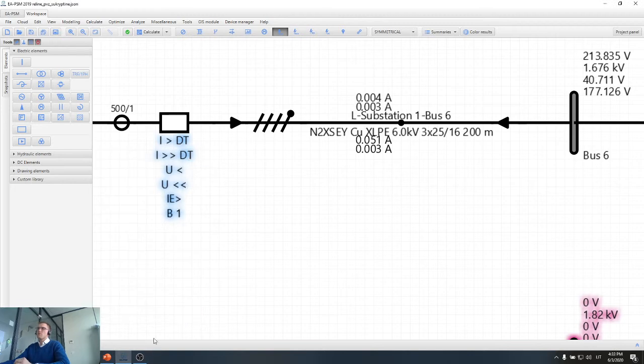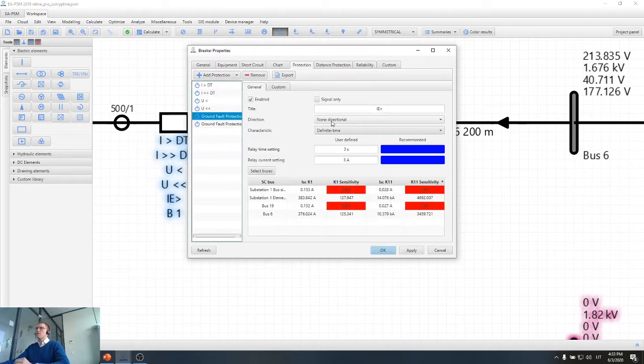So we also need to make sure that our earth fault setting of the first stage, where we set 3 amps here, is also bigger than the self-capacitive current. So these are several important criteria to check: what is the self-capacitive current, what is the error of the zero sequence transformer, and according to this we can set the ground fault current rating. Here I will provide the earth fault current 2 times more.